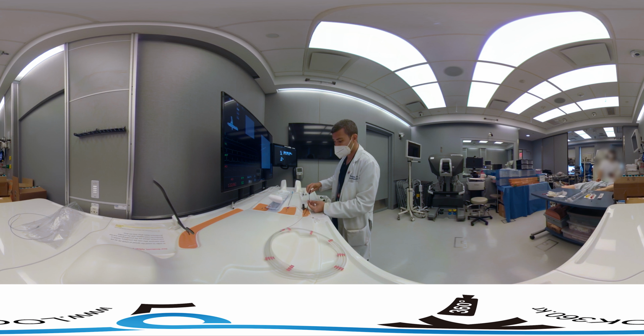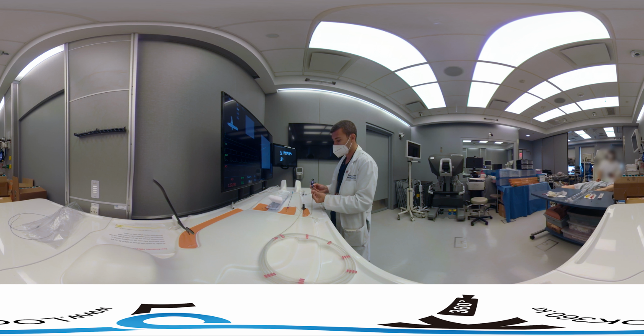Once you get into the arteriotomy, then you're going to pull out the wire. So the wire will be pulled out of the patient. And you'll just introduce the rest of this catheter, this device, until you no longer see any bleeding. And this is after the sheath has been removed. The first step is this number one. What you're going to do is pull back the foot plate. And then you're going to pull back, and the bleeding that you see through this indicator should stop.